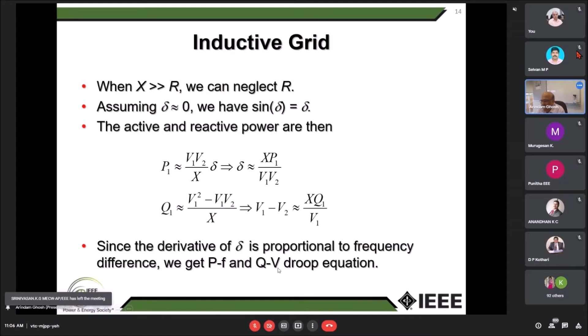So basically what we have is that delta is proportional to P, and voltage difference is proportional to Q. Now again, d delta dt is actually nothing but frequency. So what we can say, delta is somewhat related to frequency. So from that, we get the power versus frequency and reactive power versus voltage magnitude droop equation. So this is given by this.